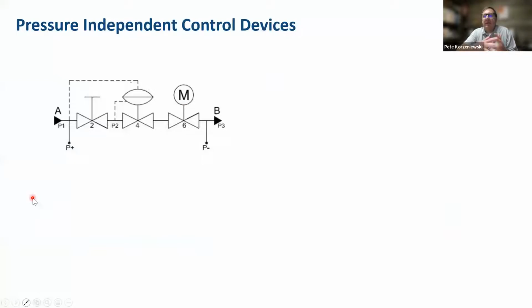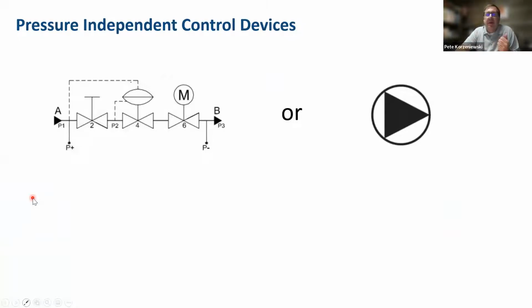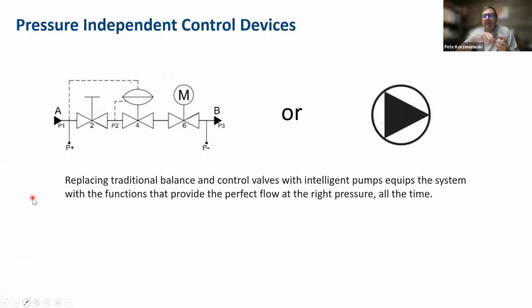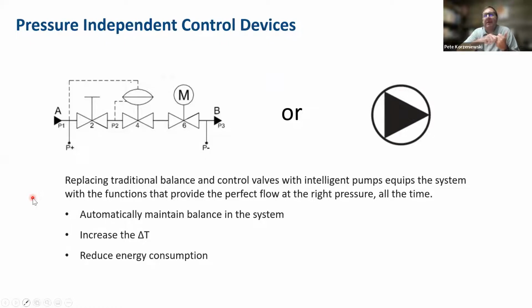So how do we deliver an optimized delta T for our building without wasting hydronic distribution energy? Well, we do it with a pump. I think a little bit differently about systems, about how we set up and balance the building loads. We might consider that a pump is easy to set up and has the capability to automatically maintain balance in the system, increase the delta T, and ultimately reduce overall energy consumption for the building.